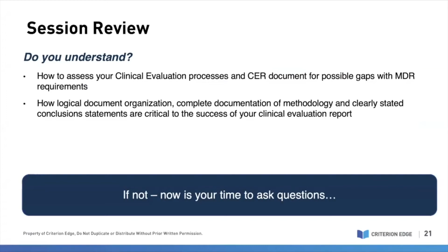So Lori, the first question is, can we use a device, equivalent device, for technical and clinical comparison and another device, benchmark device, for biological comparison under the MDR? The short answer is no. And I assume that, yes, so this is an equivalence question. And the short answer, which I hope most of us on the call are aware of by now, is that if you have an equivalent comparator, it must be one device, and you must have basically full access to the technical file of that device in order to do a line-by-line comparison of each device characteristic.